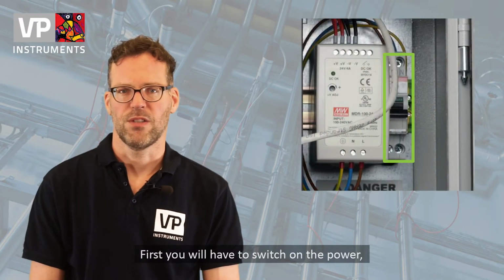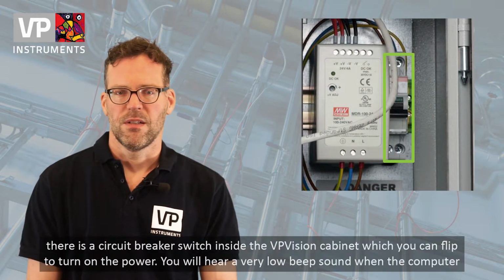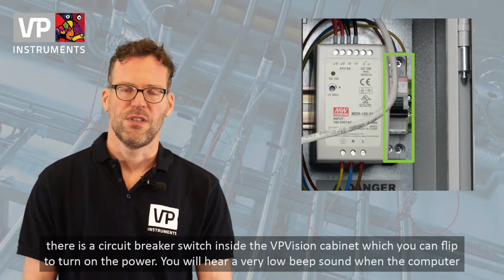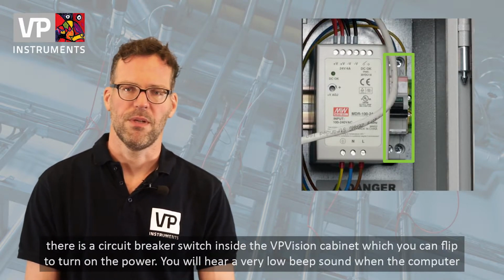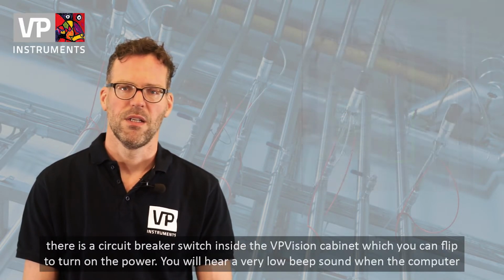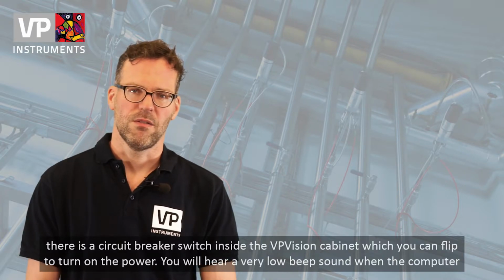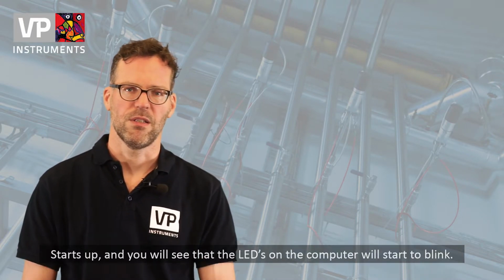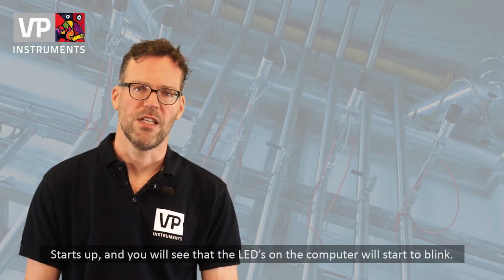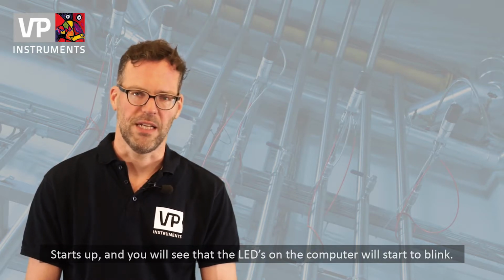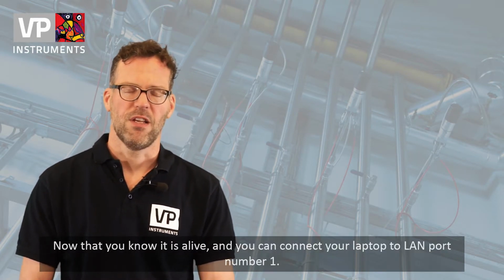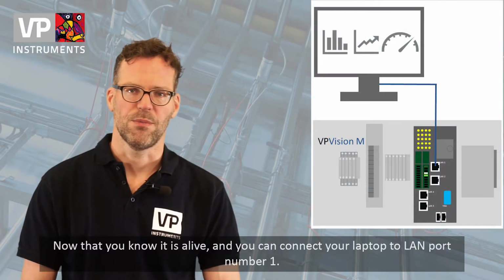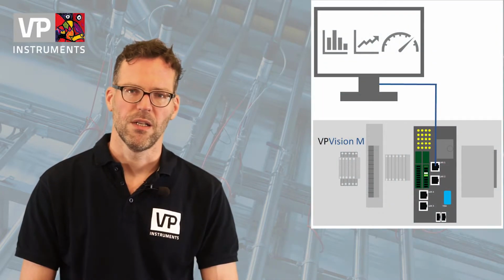First you have to switch on the power. There is a circuit breaker switch inside the VPVision cabinet which you can flip and then the power should be on. You will hear a very low beep sound when the computer starts up, and you will see that the LEDs on the computer will start to blink. Now you know that it's alive and you can connect your laptop to LAN port number 1.